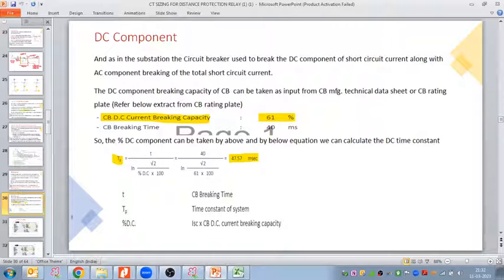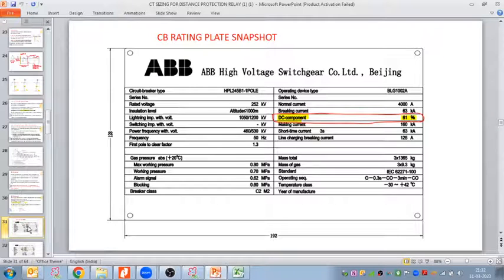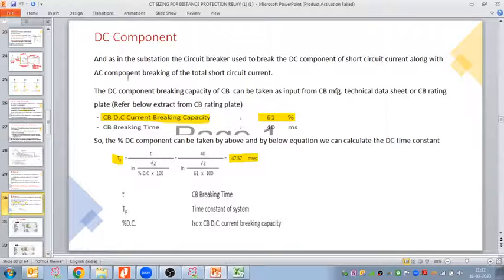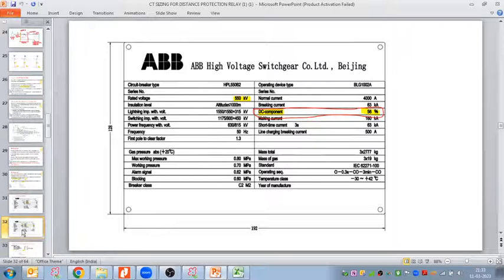Okay, and in these calculations, how much is the fault DC component? We also discussed that when you select the circuit breaker, you need to focus not only on the AC breaking capacity but also on the DC component breaking capacity. This is the ABB 220 kV circuit breaker nameplate. The DC component breaking capacity is 61 percent. So when you are calculating this DC component, you need to take the time and the DC breaking capacity. Both you need to select from the circuit breaker rating plate or the circuit breaker GTP for these calculations. All of that we discussed yesterday. This is for the 220 kV. This is for any 500 kV, right?